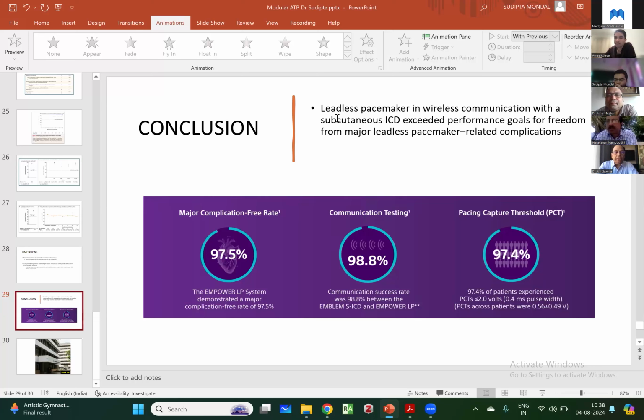Does it give atrial synchronous ventricular pacing as well, or just VVI pacing? No, this is exactly akin to a VVIR micro pacemaker. So it's passive fixation technology. There's no atrial sensing feature. So this is like the first generation Micra. This whole modular system at best is still a single chamber ICD, so you would not consider it for anybody who requires atrial pacing, AV synchrony, or BiV pacing.